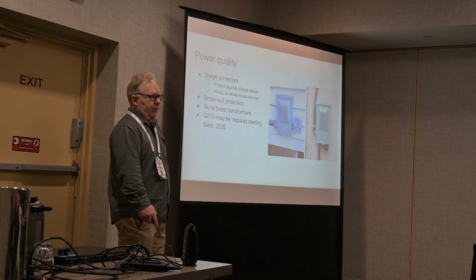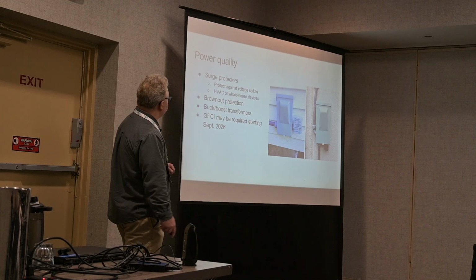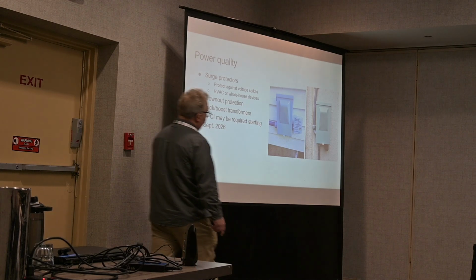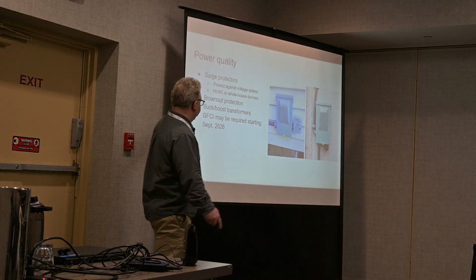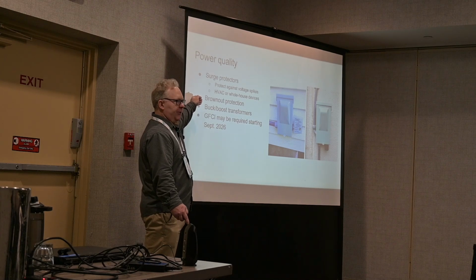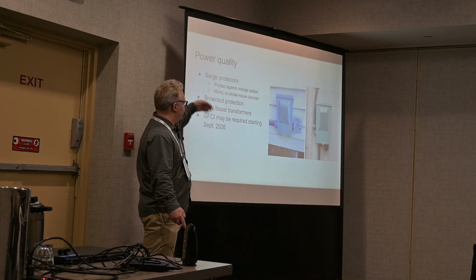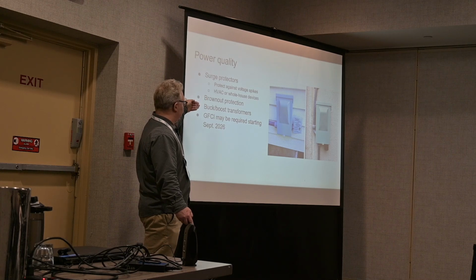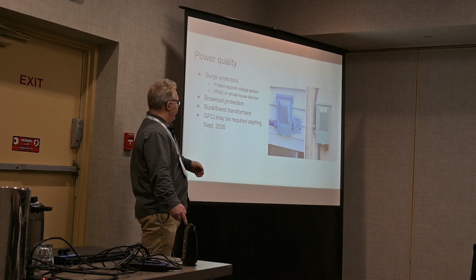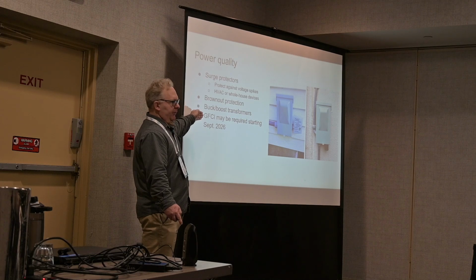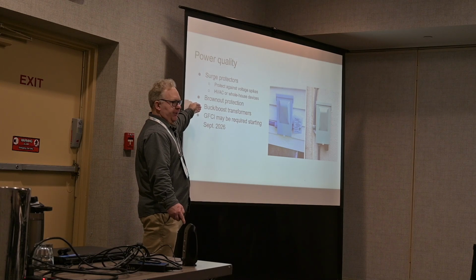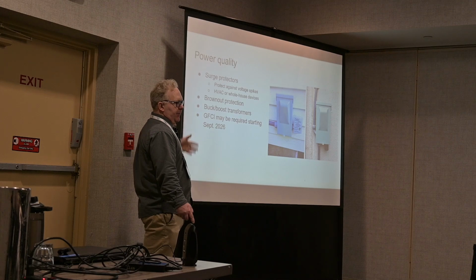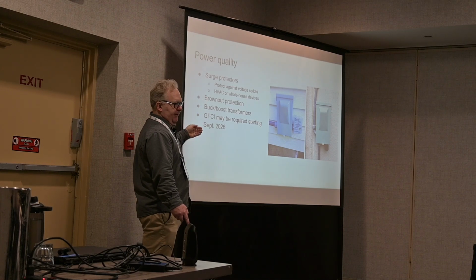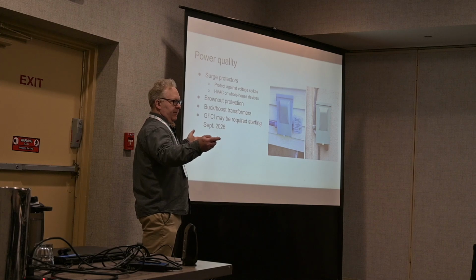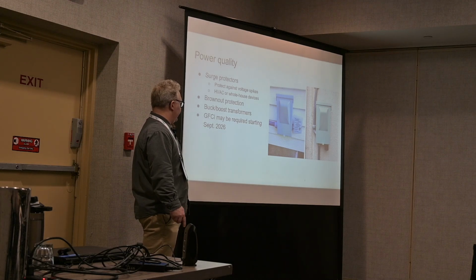Power quality is really important for heat pumps. They have a lot of sophisticated electronics. So at a minimum, every heat pump should have a surge protector. In areas where you've got brownouts, you may also want to include brownout protection that shuts the system down if the voltage falls below recommended levels. If you've got persistent high or low voltage, you may need a buck boost transformer that can either bump up or bring down the voltage to bring it within the manufacturer's recommended range.